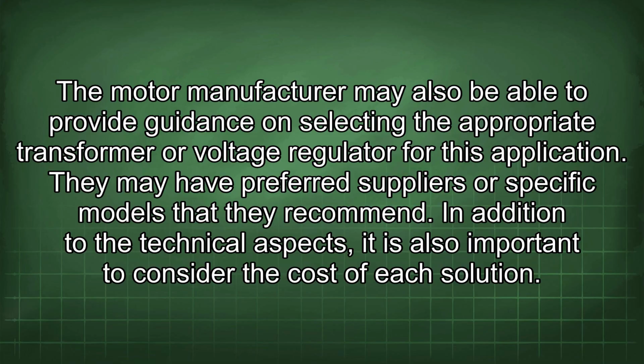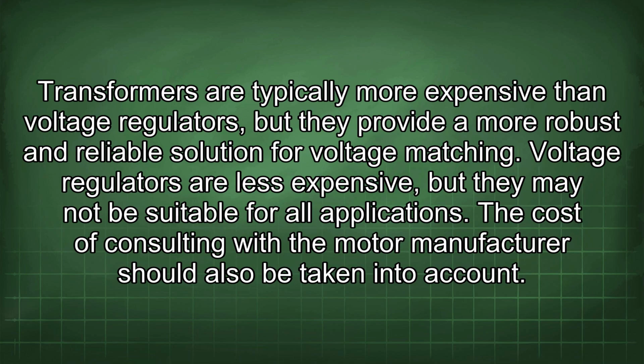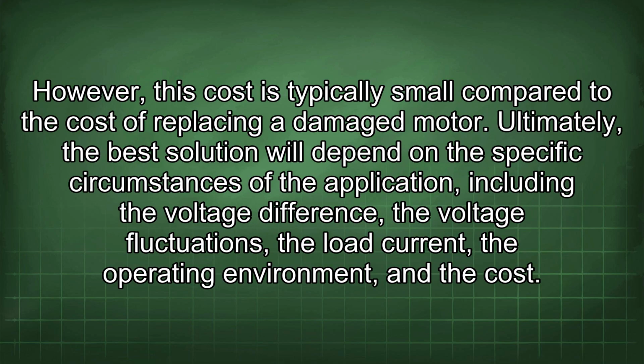In addition to the technical aspects, it is also important to consider the cost of each solution. Transformers are typically more expensive than voltage regulators, but they provide a more robust and reliable solution for voltage matching. Voltage regulators are less expensive, but they may not be suitable for all applications. The cost of consulting with the motor manufacturer should also be taken into account. However, this cost is typically small compared to the cost of replacing a damaged motor. Ultimately, the best solution will depend on the specific circumstances of the application, including the voltage difference, the voltage fluctuations, the load current, the operating environment, and the cost.